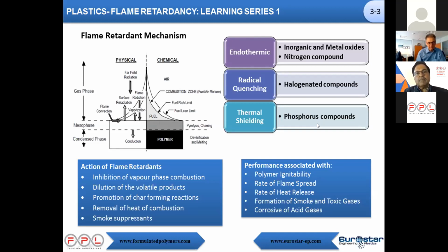In the UL standard, they call it unattended device, because basically, if this device can catch fire, maybe you are not there in the room, or maybe it's under the cabinet, it's nesting, and it will be very hard. And corrosive acid gases are very important for people who are dealing with telecommunication, for example, because you have to know that in a telecommunication terminal, fire is not so much feared, because when it's on fire, then the terminal is not working anymore.